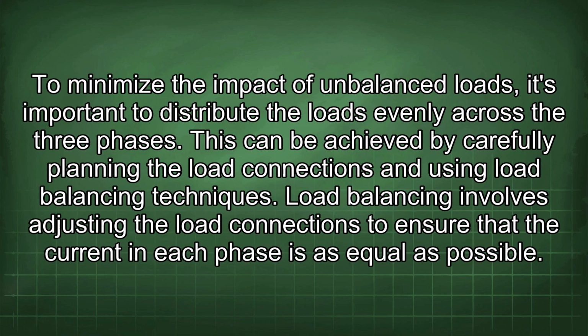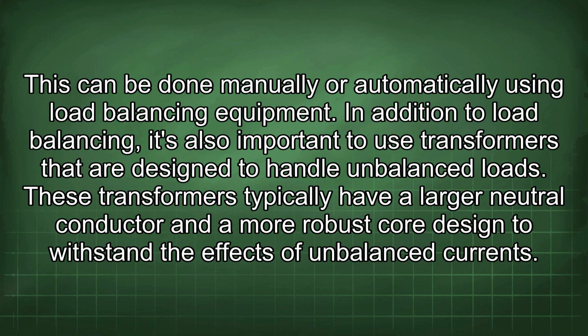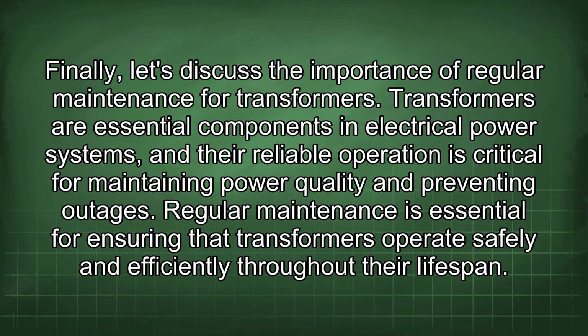To minimize the impact of unbalanced loads, it's important to distribute the loads evenly across the three phases. This can be achieved by carefully planning the load connections and using load balancing techniques. Load balancing involves adjusting the load connections to ensure that the current in each phase is as equal as possible. This can be done manually or automatically using load balancing equipment. In addition to load balancing, it's also important to use transformers that are designed to handle unbalanced loads. These transformers typically have a larger neutral conductor and a more robust core designed to withstand the effects of unbalanced currents. Finally, let's discuss the importance of regular maintenance for transformers.